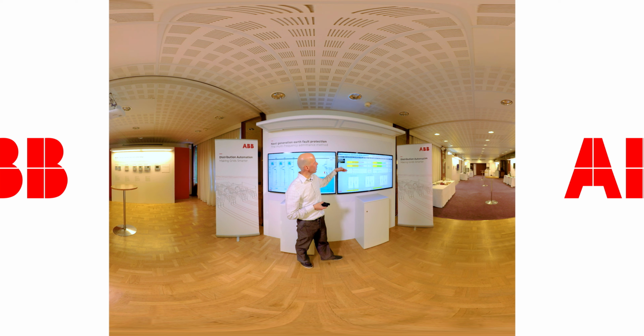But you can see here that with the admittance protection concept, regardless of the fault resistance value, we can always measure the value which is based on the value of the parallel resistor of the coil. And in the multifrequency admittance we have a settable current threshold, and it is set very simply based on this parallel resistor value. In this case, our setting was 3 amperes when the parallel resistor was about 8.6 ohms.